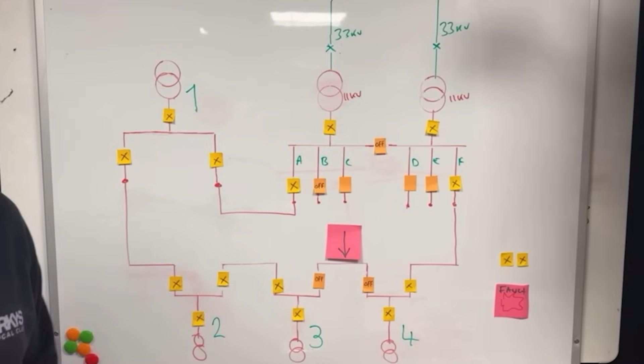But if we undo this one like that, and make that off, and we open this one like that, and make that off, you'll see that we have isolated the section of cable we wanted to isolate, and at no point during that process did the power go off to any of the transformers. So watch it again if you have to, but you'll see it never went off.